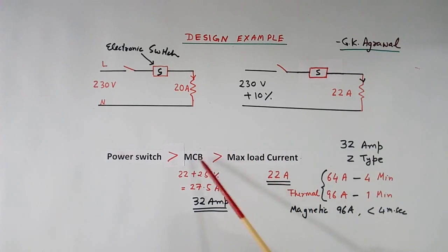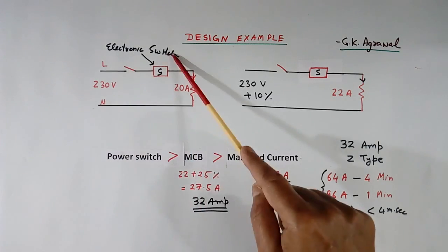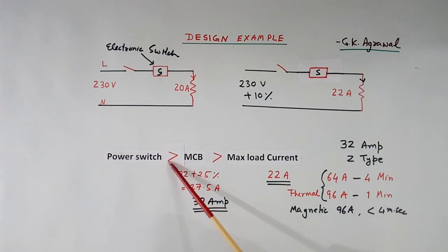So load current maximum is 22 A. MCB rating should be more than load current. And power switch rating should be more than MCB. Now load current is 22 A. Generally MCB is taken about 25% more than this. You can decide your own way. Then this current becomes 27.5 A. So MCB rating should be 27.5 A, but you will not get this rating. MCBs are made in standard currents only. Say you may get 32 A. So you will have to use MCB of rated current 32 A.